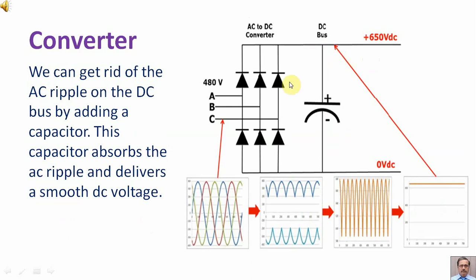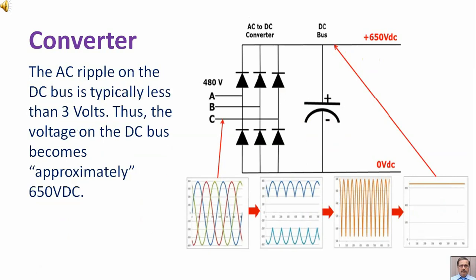We can get rid of the AC ripple on the DC bus by adding a capacitor. This capacitor absorbs the AC ripple and delivers a smooth DC voltage. The AC ripple on the DC bus is typically less than 3 volts, thus the voltage on the DC bus becomes approximately 650 volts DC.